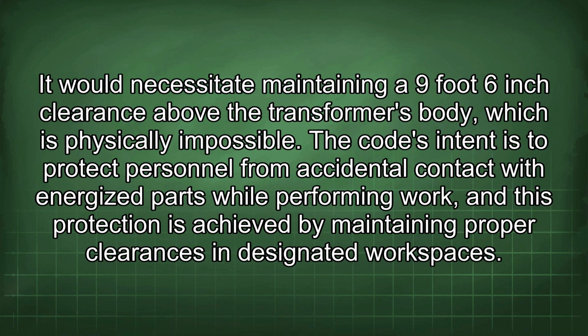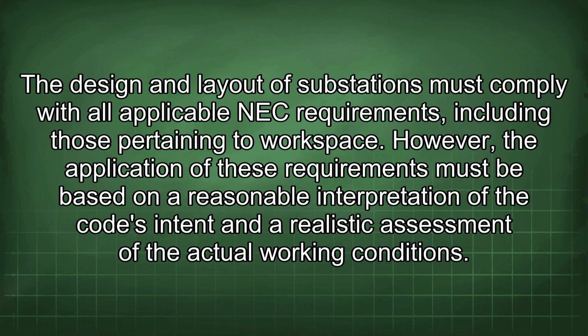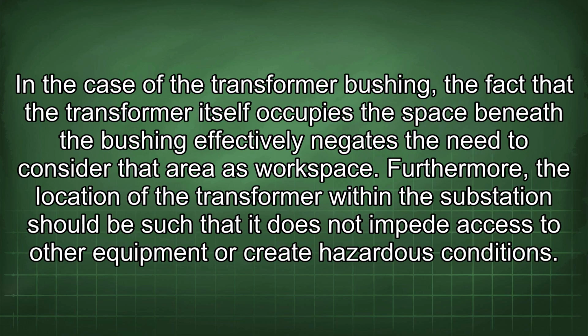The code's intent is to protect personnel from accidental contact with energized parts while performing work, and this protection is achieved by maintaining proper clearances in designated workspaces. The design and layout of substations must comply with all applicable NEC requirements, including those pertaining to workspace. However, the application of these requirements must be based on a reasonable interpretation of the code's intent and a realistic assessment of the actual working conditions. In the case of the transformer bushing, the fact that the transformer itself occupies the space beneath the bushing effectively negates the need to consider that area as workspace.